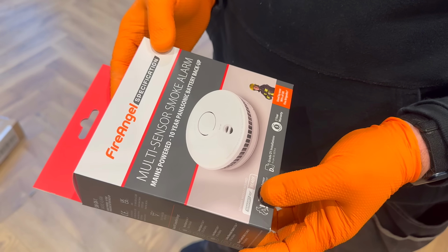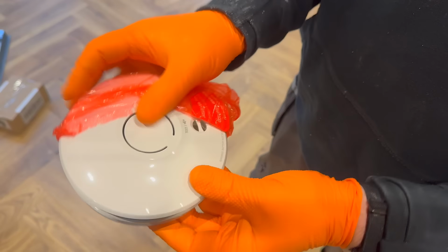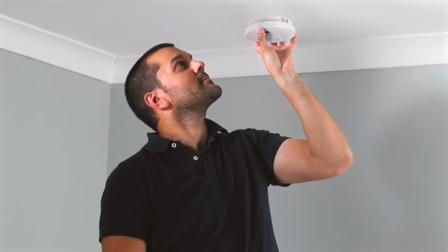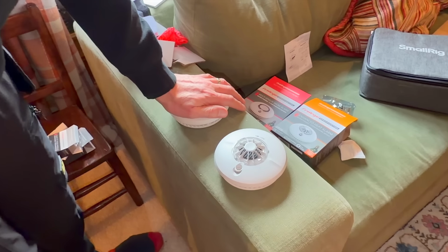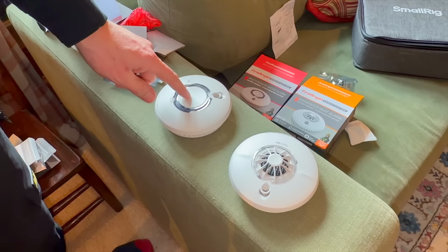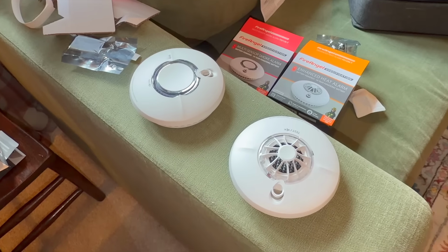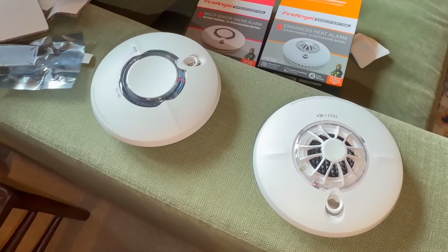Grade D1 uses mains powered alarm with a sealed tamper-proof battery. Grade D2 uses mains powered alarms with a replaceable battery backup. Grade F1 uses battery powered alarms with a tamper-proof long life battery. Grade F2 uses battery powered alarms with a user replaceable battery.